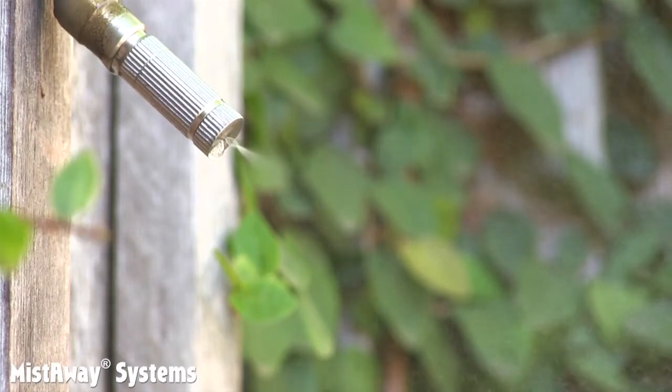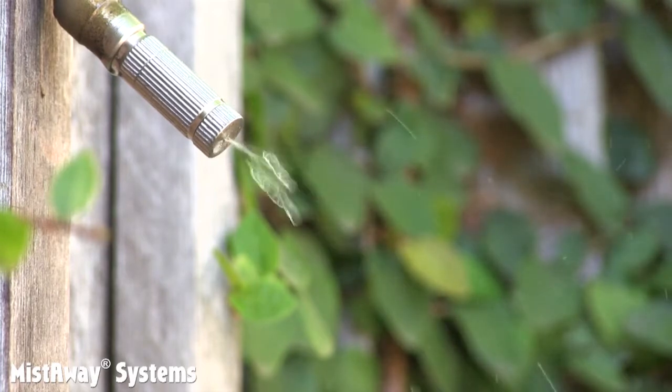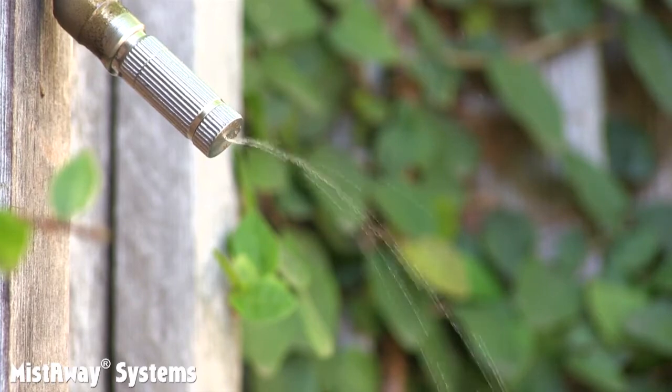At pressures below about 90 psi, the nozzle isn't really misting. It's streaming or dripping, which looks like this. As the flow gets smaller, it takes longer for the pressure to drop and the nozzles to close, and the streaming and then the dripping can go on for a very long time, until the pressure drops enough for the ball to seat in the nozzle inlet and close completely.